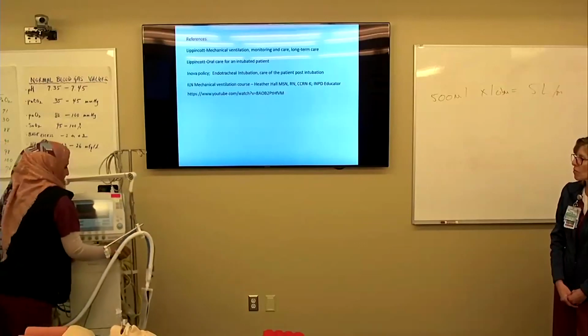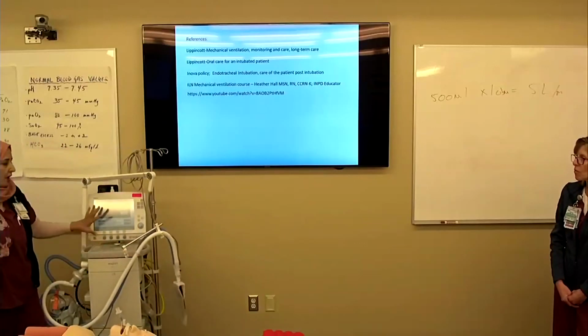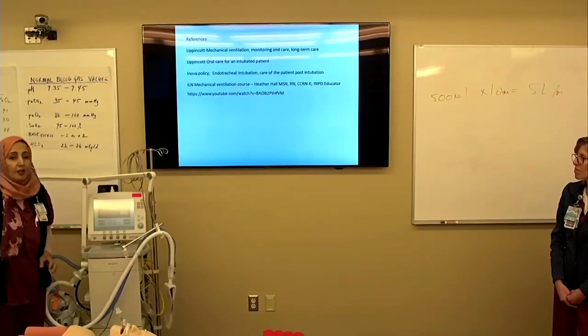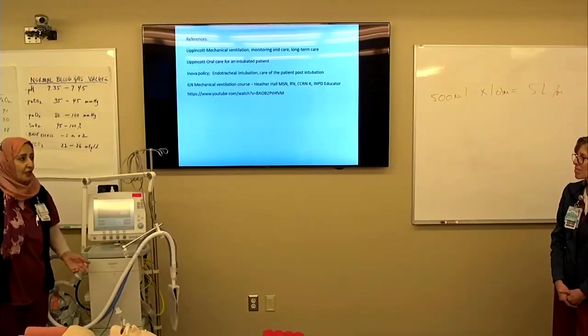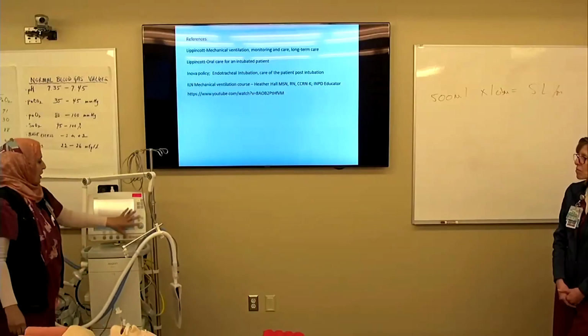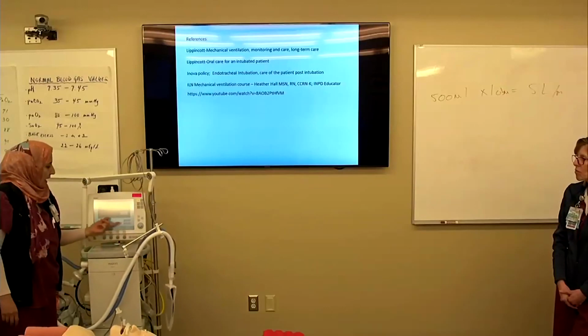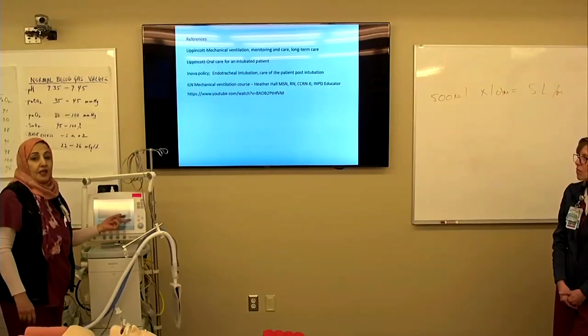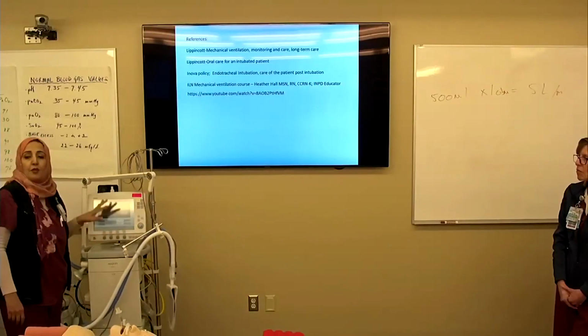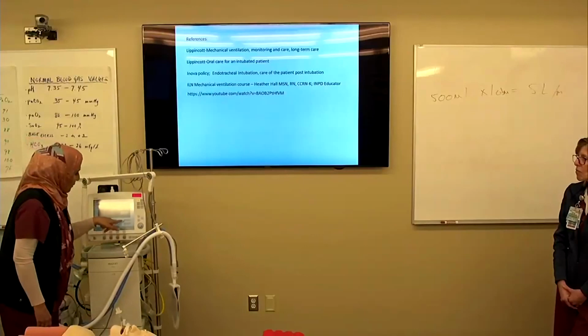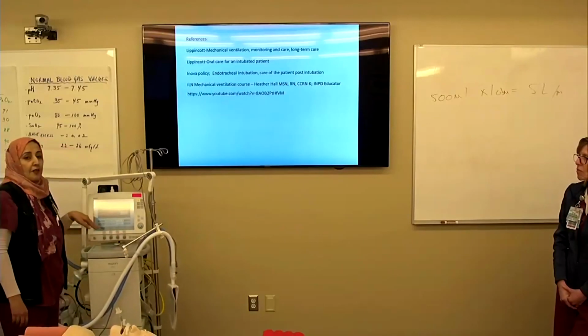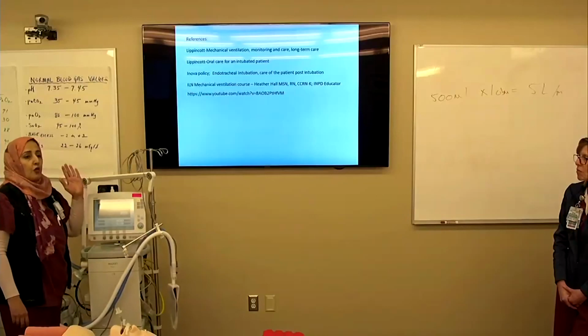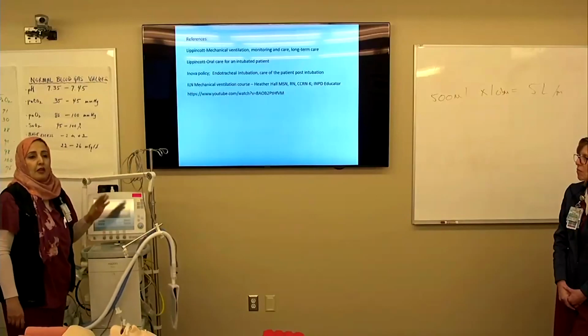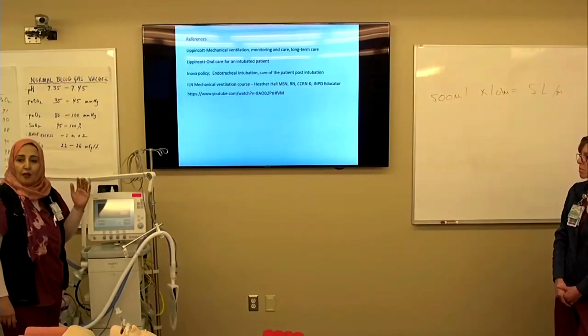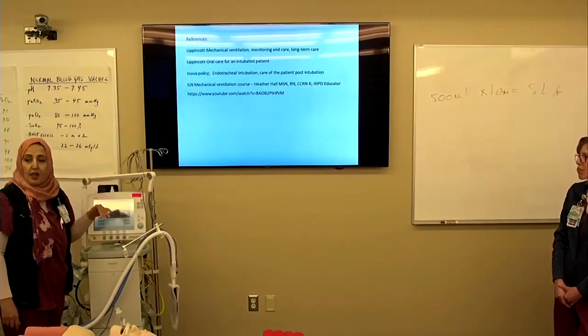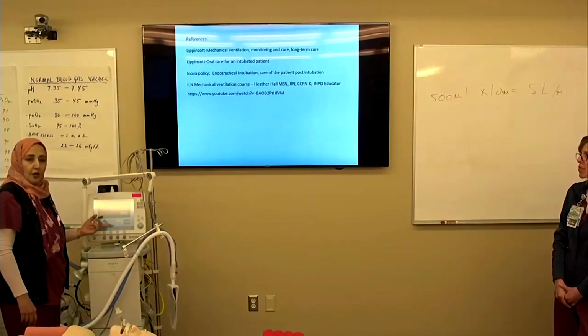In the front, for you as nurses, Dr. Mahajan talked in great detail about mechanical ventilation, so I'm not going to repeat anything. I'm just going to show you the most important things in general. We have the adult button and we have the pediatric. So it's really important before you turn on the vent to see which mode you are in. If you're not in adult mode and you turn it on, for all the measurements that you put in for tidal volume, respiratory rate, and all that, your tidal volume cannot be more than 200 or 300. So it's very important to make sure that you are in the adult mode.